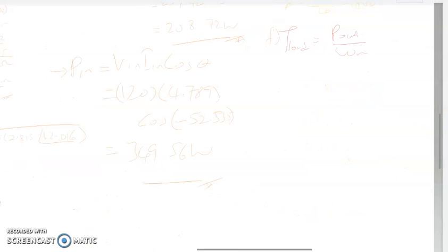Okay, next is your load torque, which is the output power divided by the speed at your mechanical shaft, the motor shaft. So we calculate P out of 208.72 watts divided by the rotational mechanical speed in radians per second, which is 1710 rpm, and so you will get 1.165 Newton meter of your output torque or load torque.